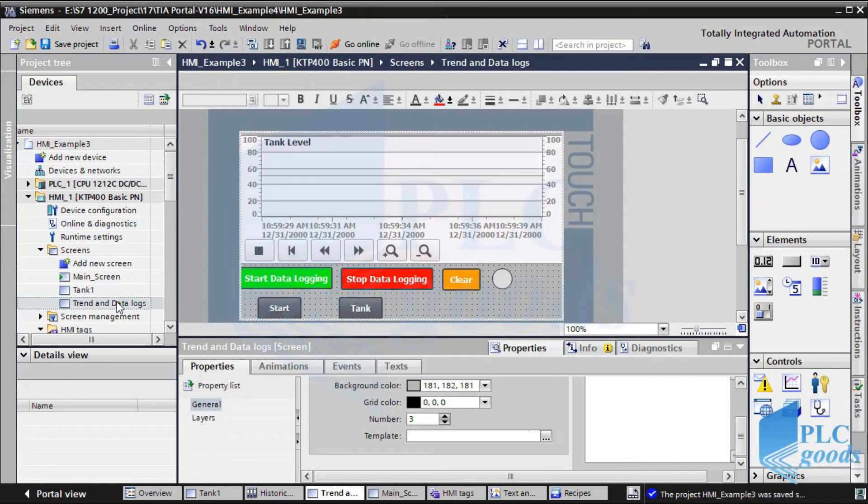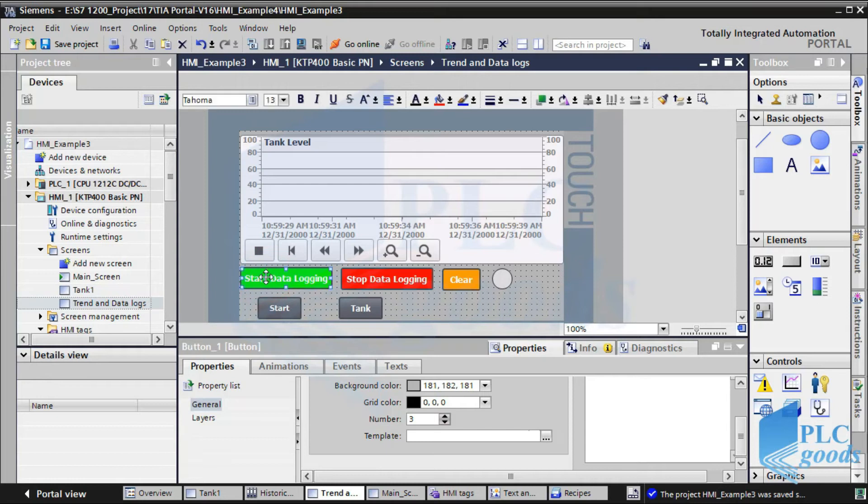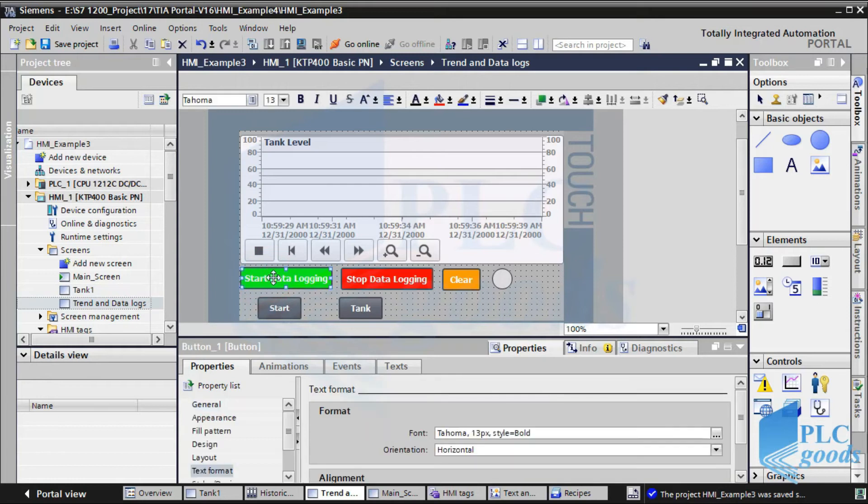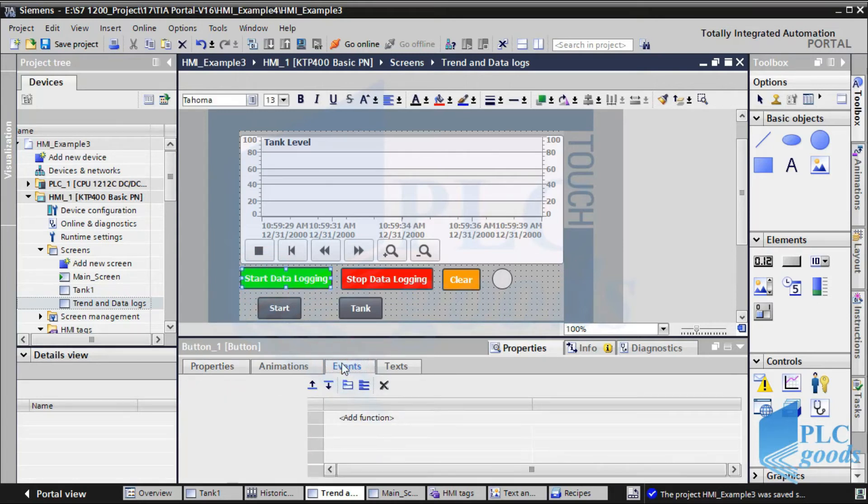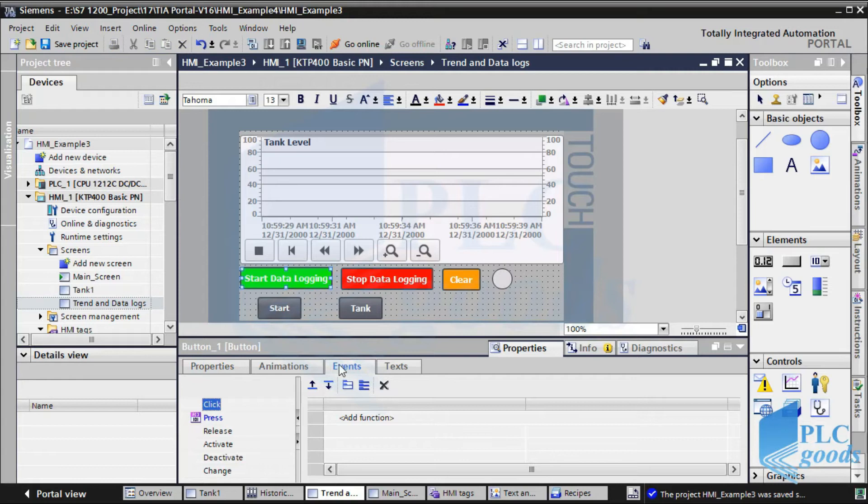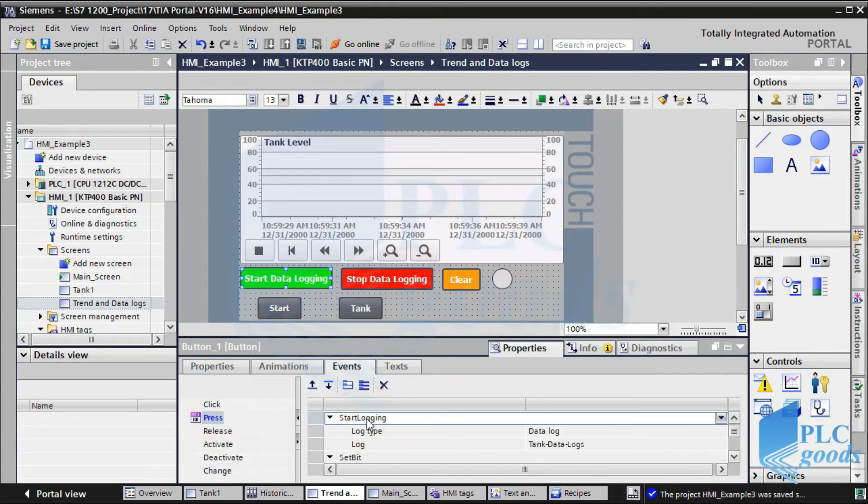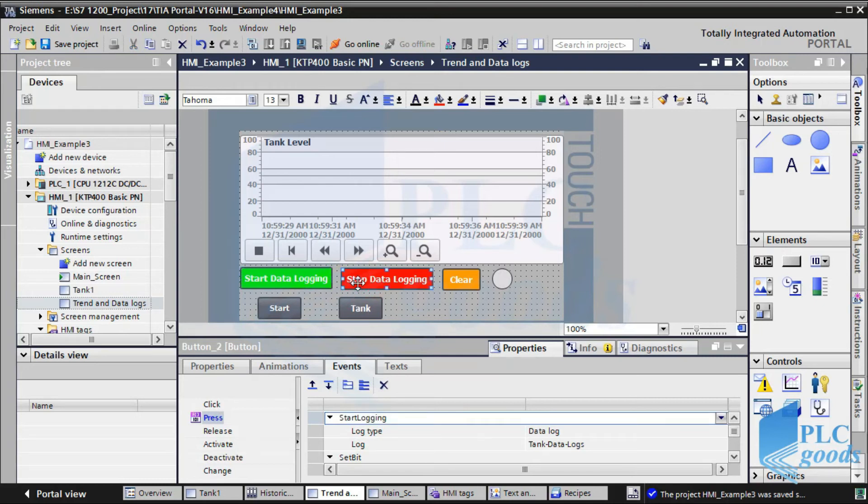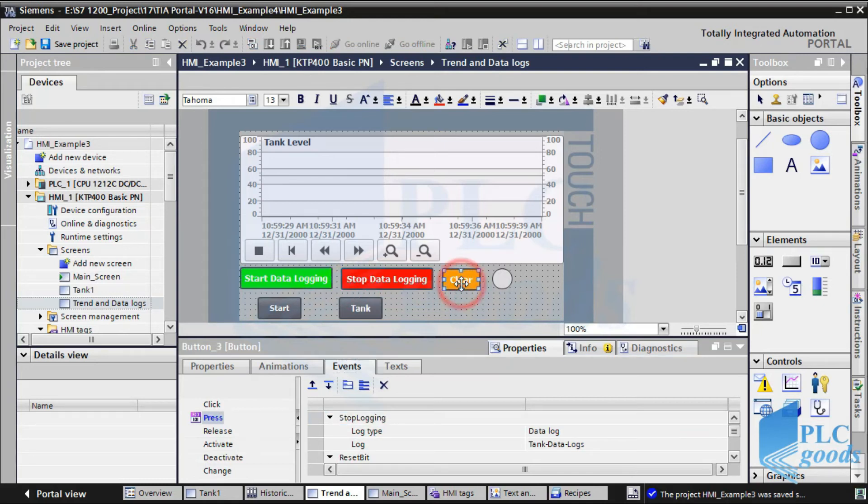First, I have created a new screen and used a trend view. The main part is three inserted buttons which are using suitable functions in their events tab. For the start button, I have selected start logging function. For the next button, the stop logging function is used. And the third button uses clear log function.